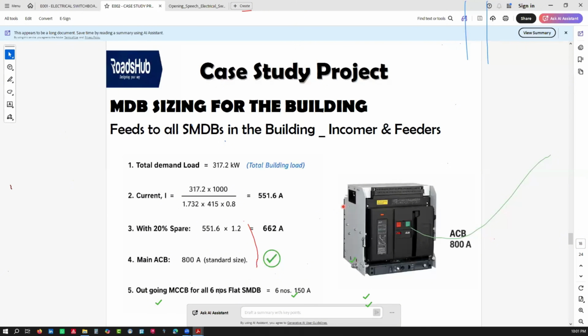So the outgoing MCCB for all the 6 flats was actually 125. But now I'll use 150. And I've told you, the reason I go a higher value is because I'm going into a system that now handles a lot of current. And now maybe you want a specific kA. And these kA values, when it comes to sensitive projects, they actually assess them. If you're building data centers, you really need to know your kA value. You can actually do a power system study for that, for a sensitive system.